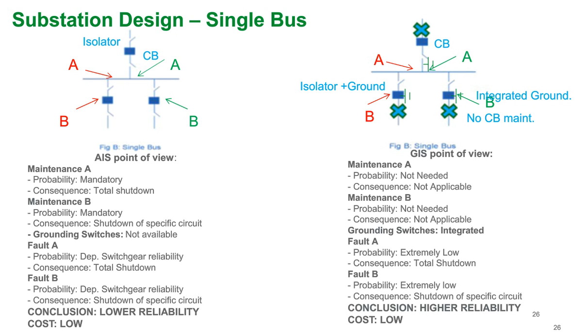With air-insulated switchgear, the reason you have routine and preventative maintenance, and a lot of these new preventative maintenance practices, is that it's assumed to be a lower reliability type of design. However, the cost of this is pretty low. When you go over to gas-insulated switchgear, the point of view there is that maintenance, of course, is not needed in the bus bar compartment or the circuit breaker. However, if there is a fault, either of the circuit breaker or of the bus, you might have a total shutdown or a shutdown of a specific circuit. So the consequence is the same, but the probability that you will have a fault or a problem in one of these compartments is very low, for a lot of the reasons we've already discussed earlier in this webinar. So the conclusion here is that for a single bus arrangement, you get much higher reliability at a still low cost, because it's a simple design.